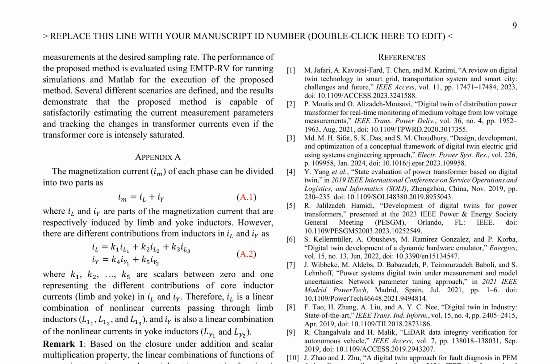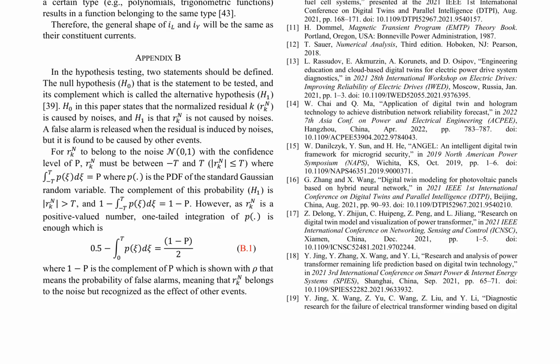satisfactorily estimate current measurement parameters and track changes in transformer currents, even in intense saturation. The magnetization current of each phase is decomposed into two components, induced by limb and yoke inductors, which are combined through linear operations to produce functions of the same type as their constituent currents.